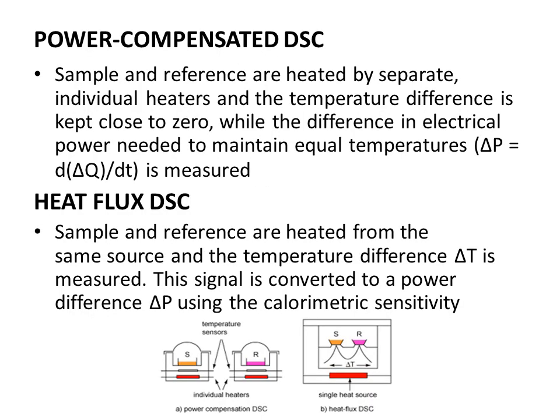In power compensated DSC, the sample and reference pans are heated separately using individual heaters. You can see in the diagram: here is the sample pan, here is the reference pan, and here are the individual heaters. Both pans are heated individually and the temperature difference is kept close to zero.